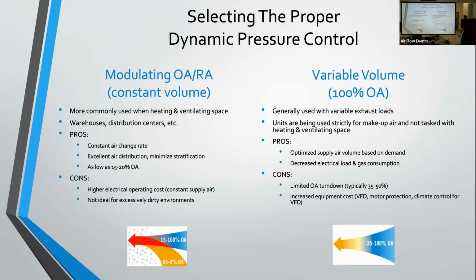So looking at variable volume units, 100% outside air variable volume units. These are typically going to be used when you have varying exhaust loads in the space. And the units are strictly used for makeup air for that exhaust load, and you're not trying to heat and ventilate the space with these makeup air units. That's not all encompassing. That's just kind of a general application guideline that I try to follow. Some obvious pros with variable volume units are the fact that, okay, you've got a unit that's designed for 50,000 CFM, but you can run it down to half of that air volume. Obviously, you're seeing a significant savings because you're running that unit at a lower brake horsepower and a lower electrical load on the unit.